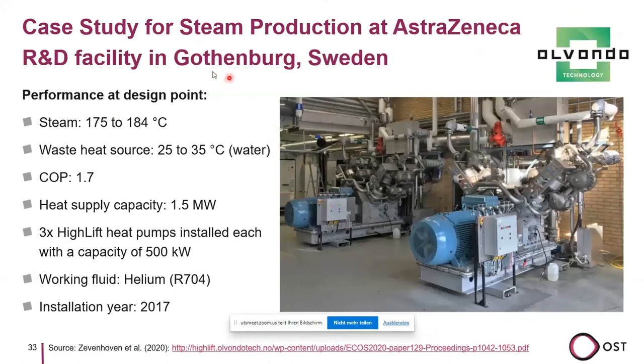One case study of this high lift heat pump is at AstraZeneca in Sweden. They produce steam at 175 degrees from waste heat of 35 degrees. The COP reached is 1.7, and they have three such units installed in parallel, so they can increase the heat supply capacity to 1.5 megawatt, because each is around 500 kilowatt.